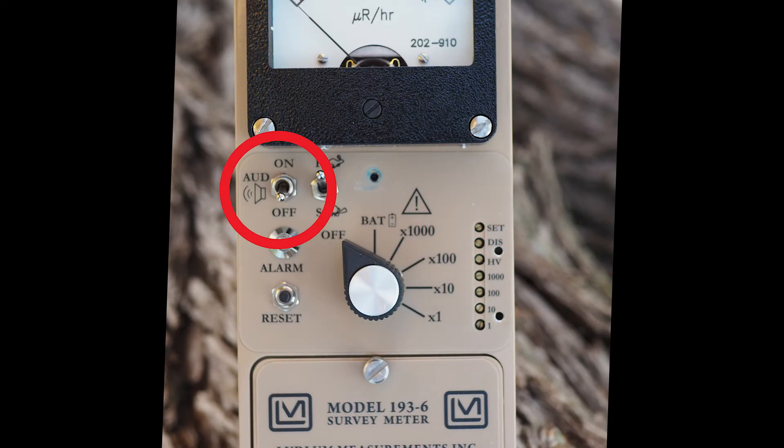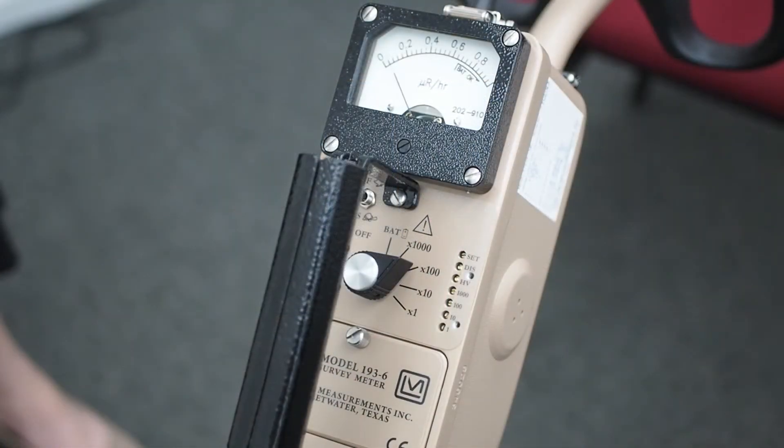The audio on/off toggle switch is used to silence the clicks coming from the speaker located on the left side of the instrument. The frequency of the clicks is relative to the rate of the incoming pulses.